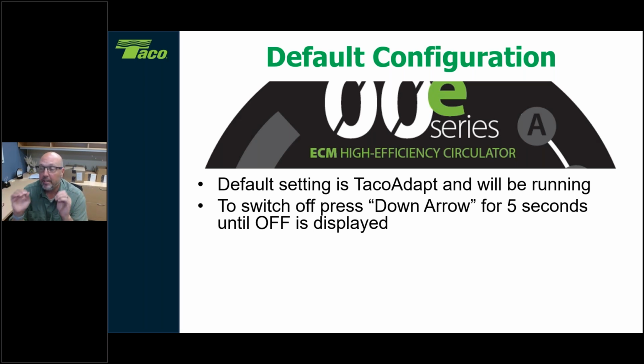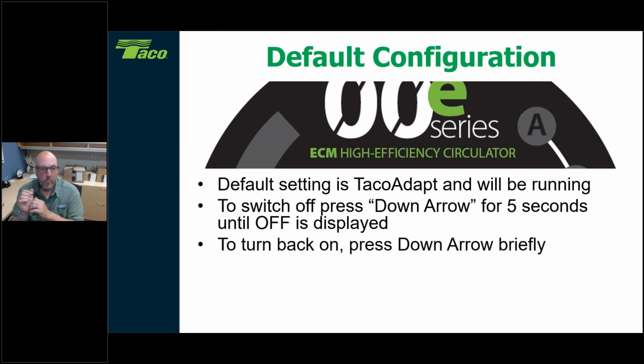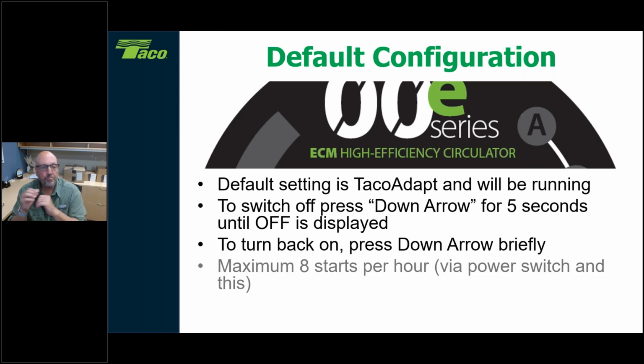All right, and you don't have everything all done just yet. You put power to it. Make sure that there's water in the system. Okay, that is very, very important. All you need to do to get it back running again is touch the down arrow again. You don't have to hold it for 5 seconds. You just touch it, and the circulator will go back into TacoAdapt mode. Again, it's going to be running in the default mode until you change those settings.